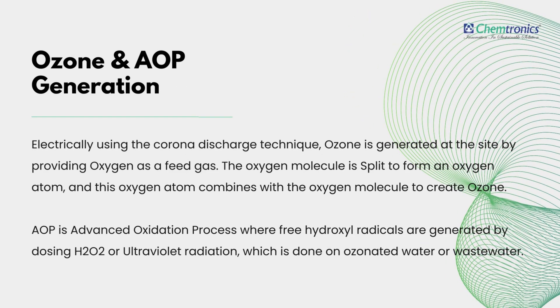Principle of Generation of Ozone and AOP. Electrically, using the corona discharge technique, ozone is generated at the site by providing oxygen as a feed gas. The oxygen molecule is split to form an oxygen atom, and this oxygen atom combines with the oxygen molecule to create ozone. AOP is an advanced oxidation process where free hydroxyl radicals are generated by dosing H2O2 or ultraviolet radiation, which is done on ozonated water or wastewater.